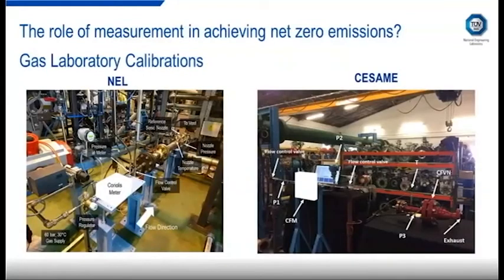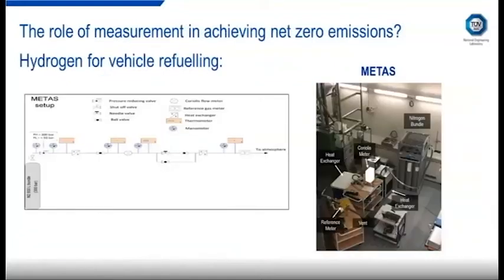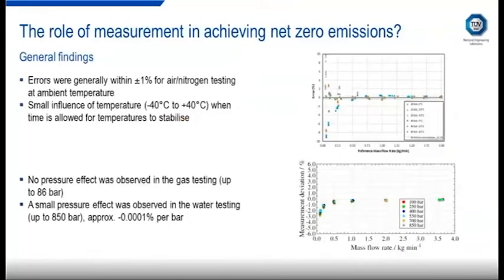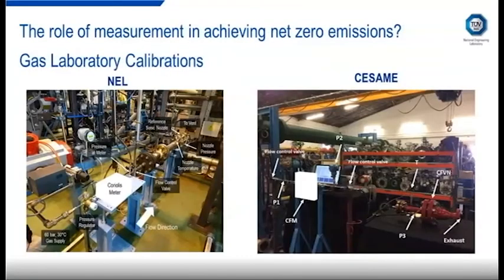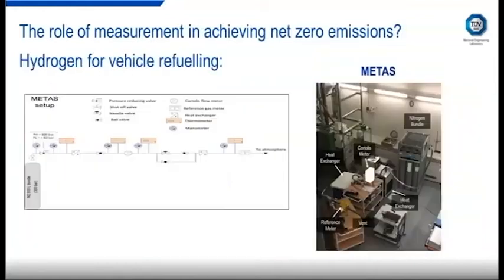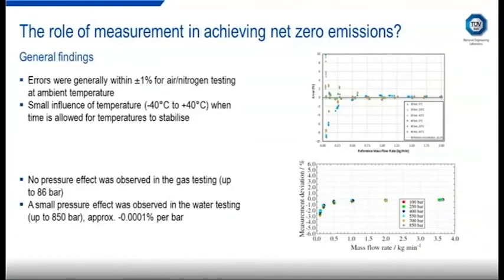So you can see some of the gas laboratories which were used for the experiments. We can see the National Engineering Laboratory, or the NEL test setup on the left. We have CESAME on the right, and we have METAS as well. And each of these installations were quite similar. We all operated in gas blowdown as an open loop. The reason for this is that the pressure drop across the flow meters was very large, in some cases up to 10 bar. So we couldn't operate in a closed loop configuration, and we all used either nitrogen or air for these tests.